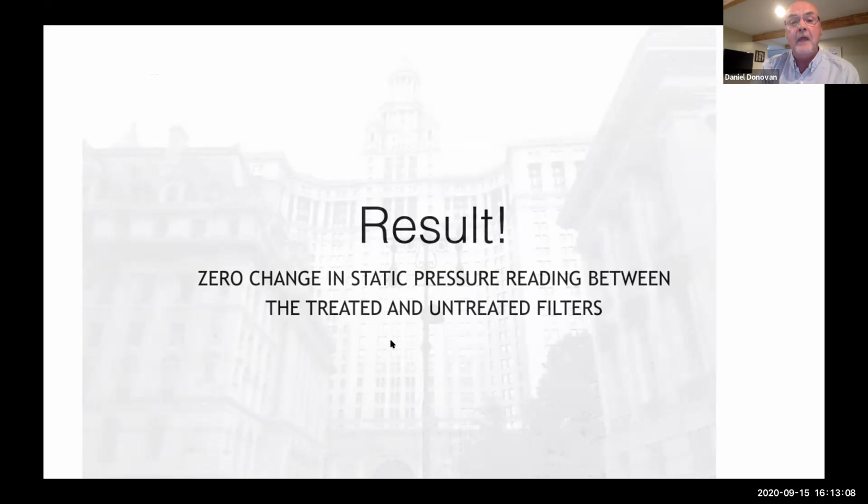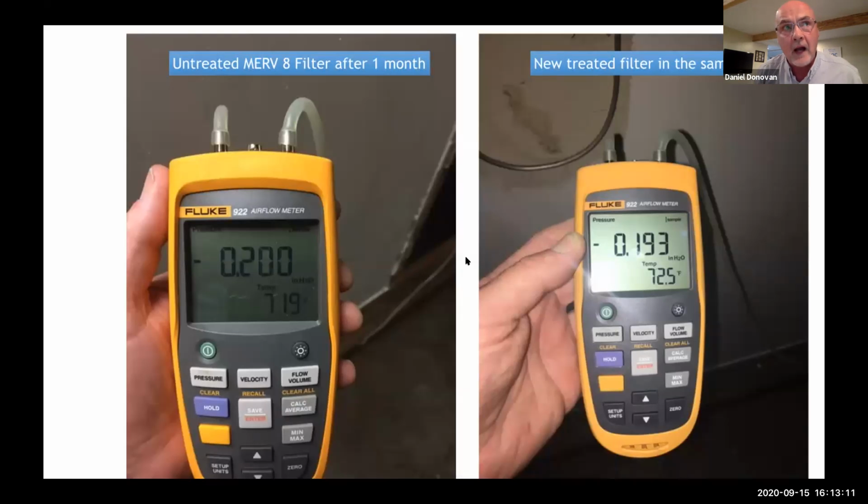And the main one that I did was a 40,000 CFM air handler with 24 by 24 by 2 MERV 8s. And we actually recorded that from beginning to end. And in the interest of boredom, we sped up the filter change, the guys doing the filter change. And Don will be very happy if he ever sees the video. We put the clips back in every single one of them. And that one is on video. I didn't have a photo of that. This one I actually did separately.